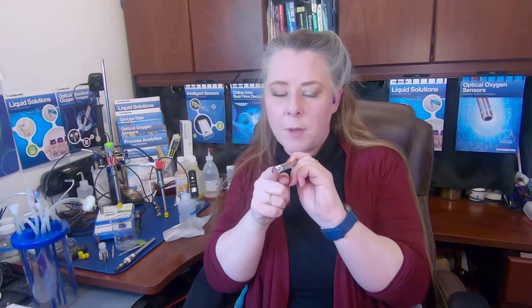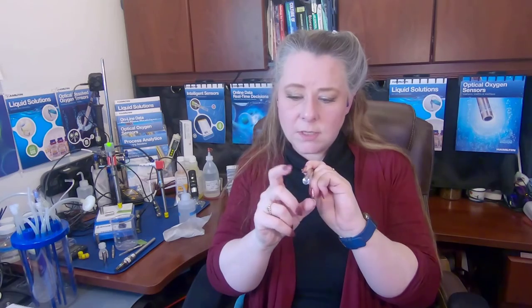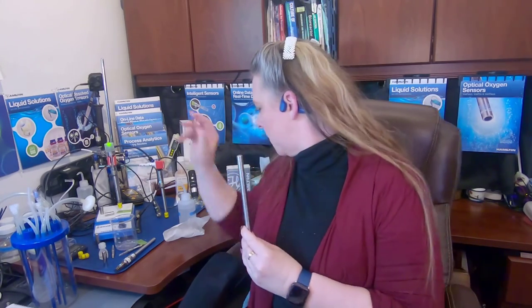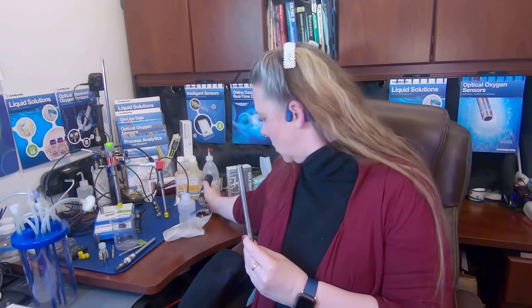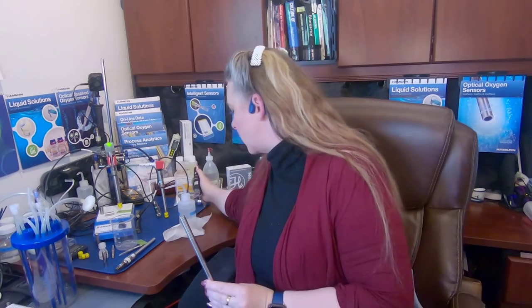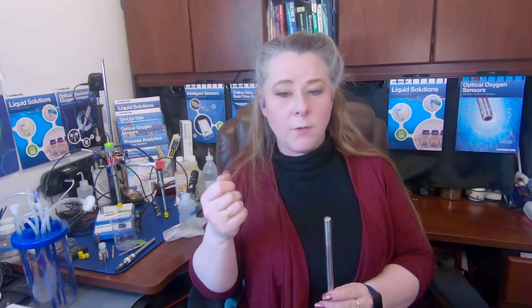But you do not want to overfill the probes, because when you autoclave them, we talked about this, too much liquid pressurizes and expands. It only has one place to go, and that's out the bottom. And if you burst this membrane cap, you've got to start over. I will also frequently visually inspect the end of that cap. I'm a geek, I admit it. I happen to have a little microscope here that pairs to my phone, and I will inspect to make sure there are no micro cracks in the tips of my sensors. Magnifying glasses work really well, if you happen to have really good eyesight. That ship sailed a long time ago with me.